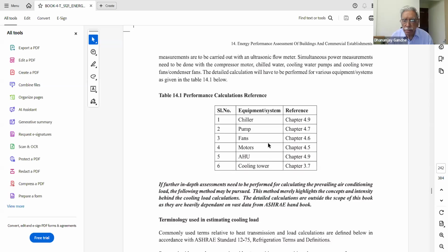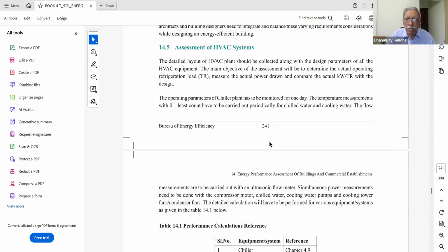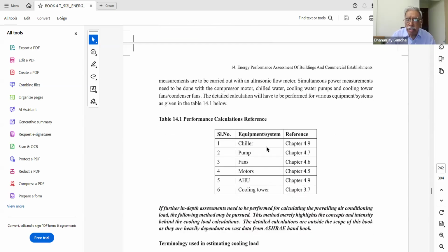Okay, and then we also make the measurements of the kilowatt. So what is the chiller kilowatt? What is the pump kilowatt? What is the kilowatt of the fans? Actual measurement. Also the motors, what is the kilowatt, and what is the AHU kilowatt, and the air conditioning tons of refrigeration load. For calculation of the refrigeration load, we have to do certain calculations. So this is what we will see later on.